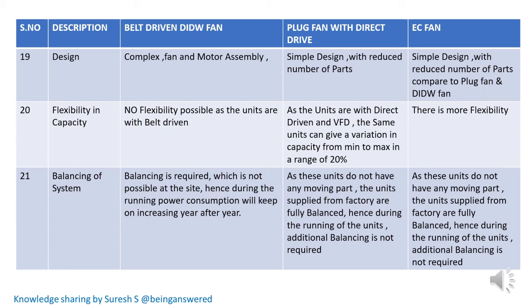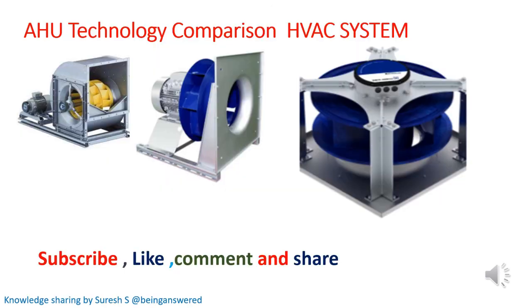For balancing of the system, balancing is required for belt driven DIDW which is not possible at site, and hence during running the power consumption will keep increasing year after year. For plug fan and EC fan, as these units do not have moving parts, the units supplied from the factory are fully balanced. Hence during running of the units, additional balancing is not required.